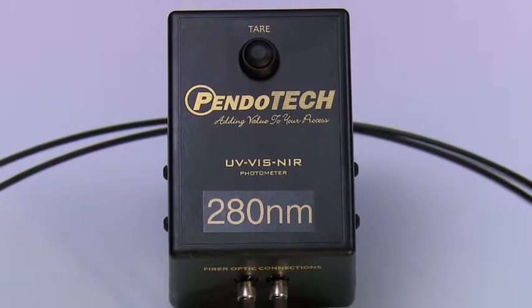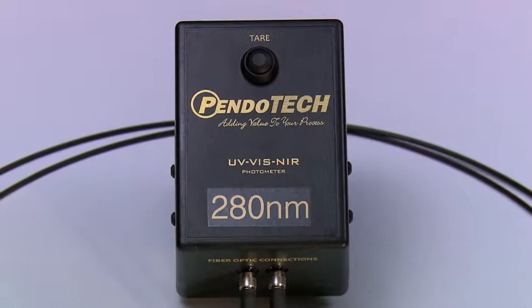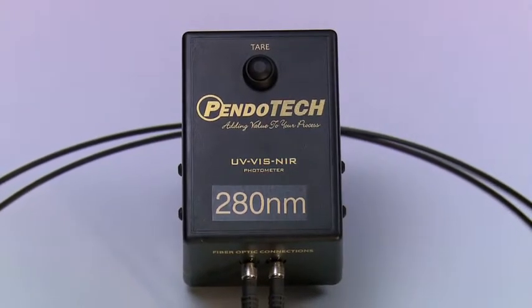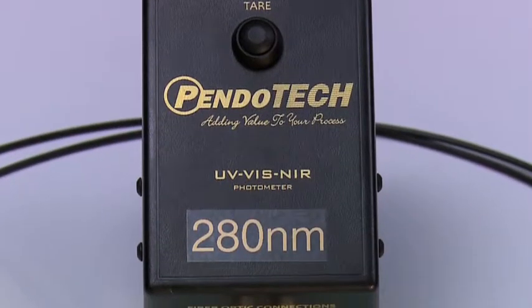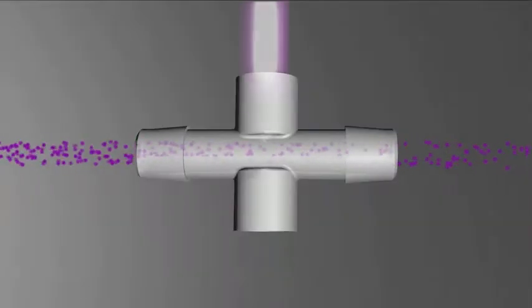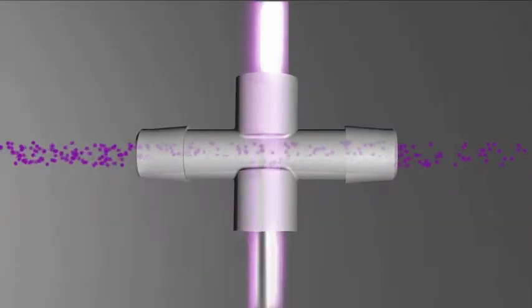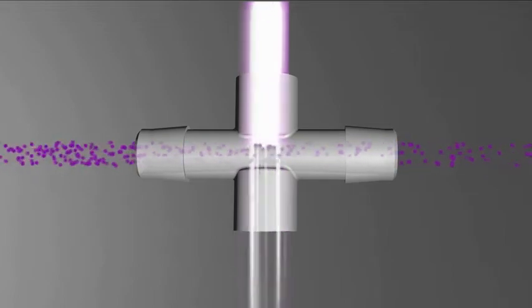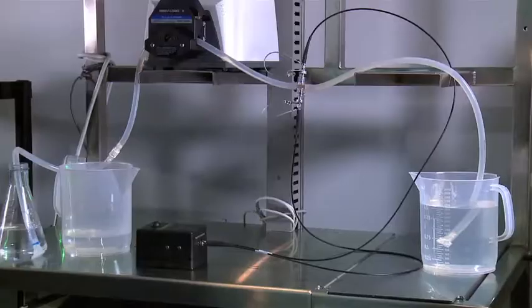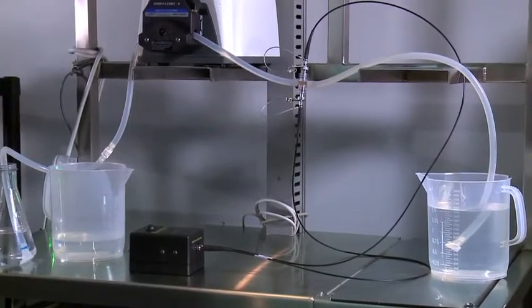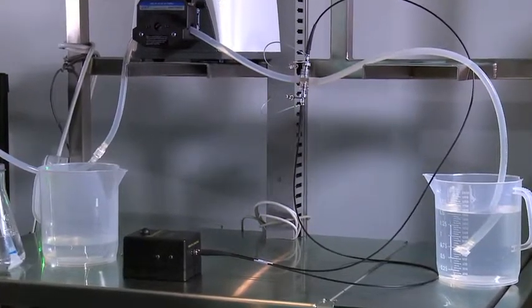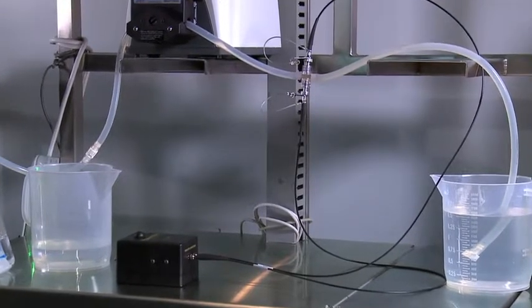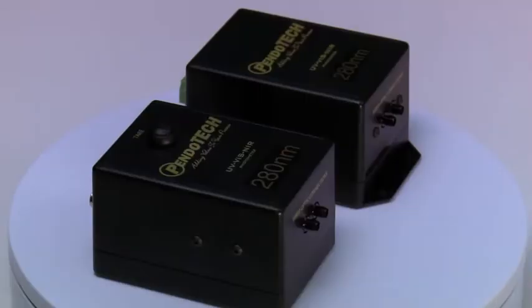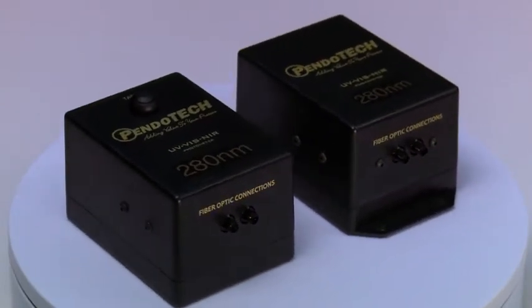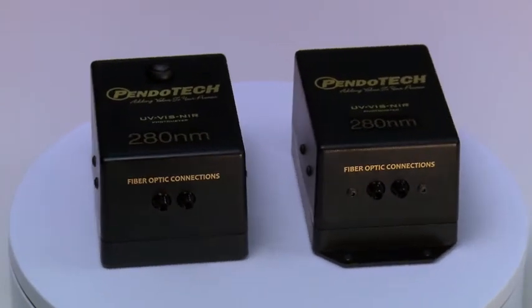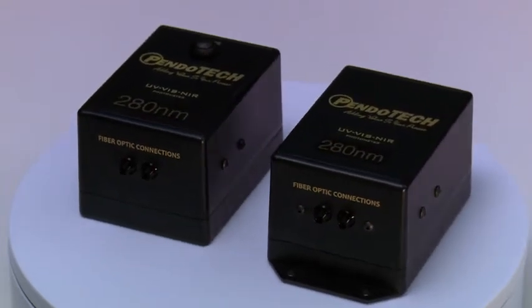The photometer provides the light source at a specific wavelength, most often 280 nanometers, but a wide range of other wavelengths can be specified. It also contains the photodetector, which determines how much light has passed through, of the light that was incident on the liquid in the cell. The light travels to the flow cell through special non-UV light-absorbing fiber optic cable and returns to the detector also through a second fiber. There are two versions of the photometer, one designed for benchtop use and one for remote mounting inside an industrial cabinet.